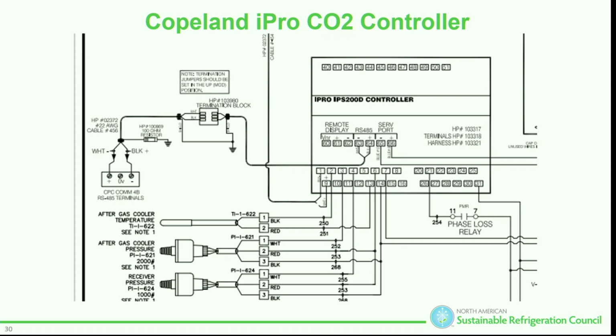So, first thing we start with. It's got to be garbage in, garbage out on any kind of controller. If I don't check the transducer, if I don't validate the transducer, if I don't have a gauge on it, if I don't validate... Anybody ever heard of one of these? Everybody ever see one of these? I've got to validate my temperature probe, yes or no? Like Brett said, if I'm using a Danfoss, I can't plug in a CPC probe; one's an NTC probe, one's a PTC probe. We've got to make sure our inputs are good. Garbage in, garbage out.